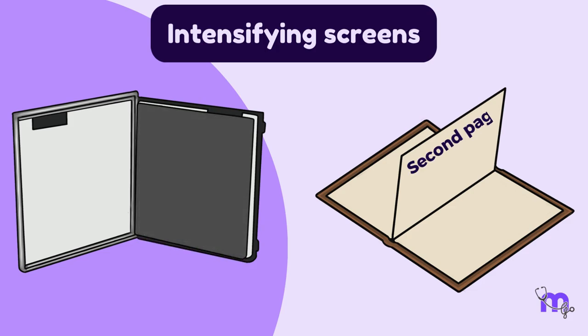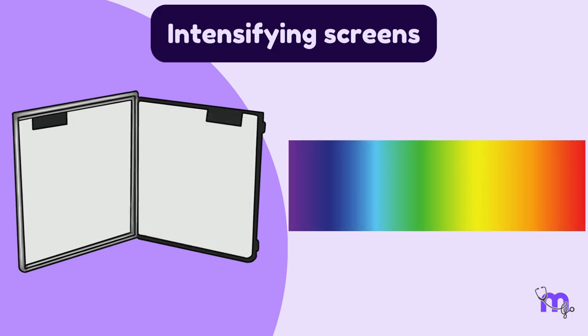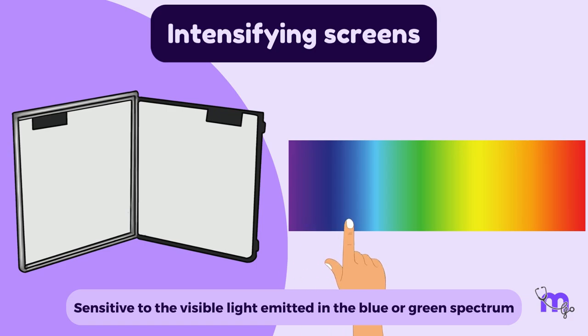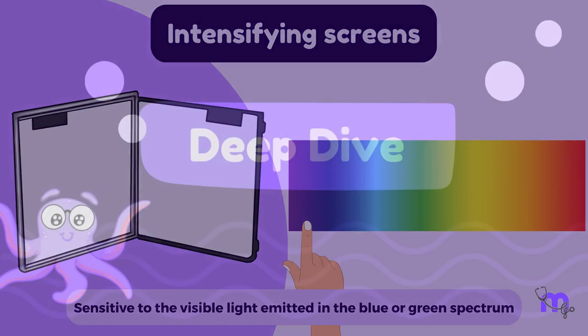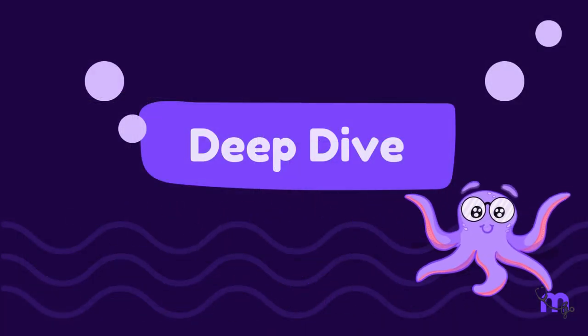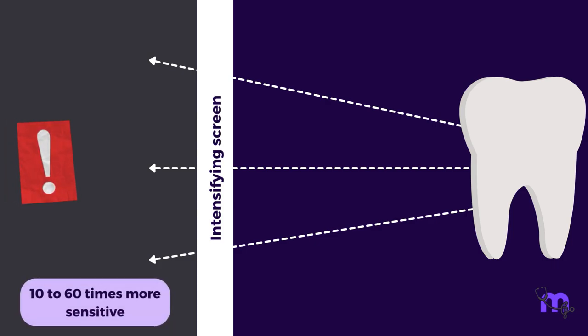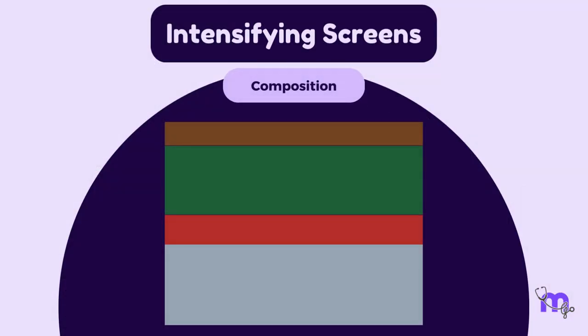The film is like the second page, positioned between these two intensifying screens. The screen films used here are sensitive to the visible light emitted in the blue or green spectrum. Intensifying screen makes the image receptor 10-60 times more sensitive to X-rays than the film alone. Consequently, the benefit is a reduced dose of X-radiation to the patient.